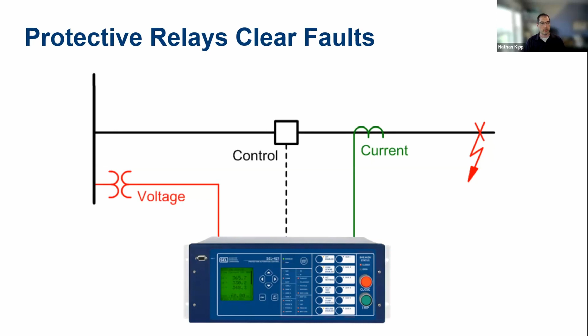So faults then, this is what relays are detecting as faults. There's a lot of different types of faults. There's asymmetric, so your power grid is generally three phases, A phase, B phase, and C phase. And an asymmetric fault will happen on one or two phases, but not all three generally. So you can have a phase-to-phase fault, which is this picture here, where we have a fault between those two phases and it causes a huge rush of current from one phase to another.